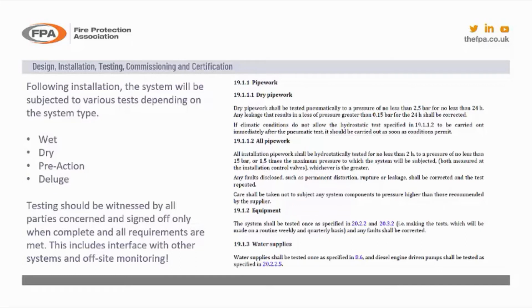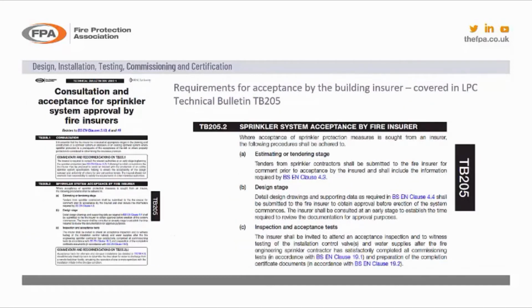And not only that, this will also include any additions to the system. If you've got interface monitoring or off-site monitoring, interfaces with the fire alarm system, or zone checks where you're testing the flow switches, these systems should all be checked, signed off and offered to all stakeholders with an interest in the sprinkler system. Again, as I mentioned, commissioning involves all stakeholders prior to handover stage. This ensures the system is checked and designed to meet the requirements to satisfy the control.